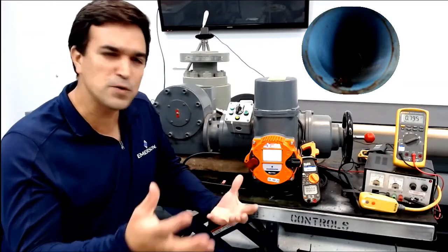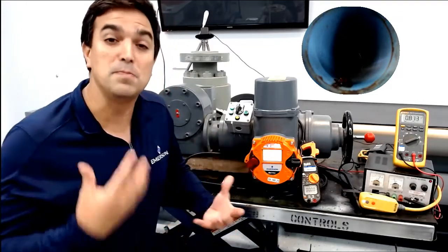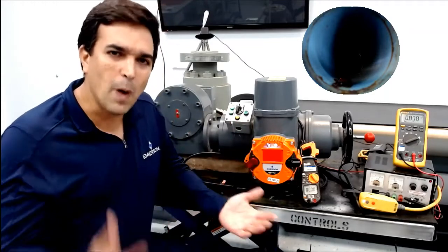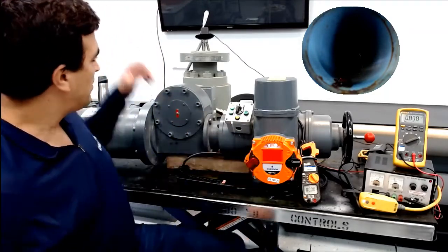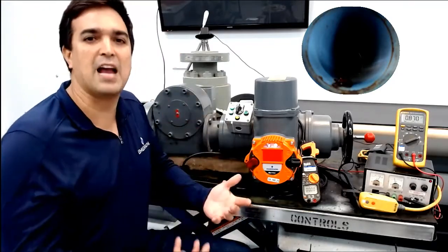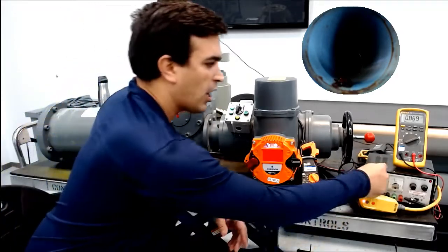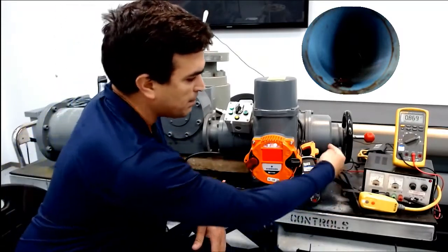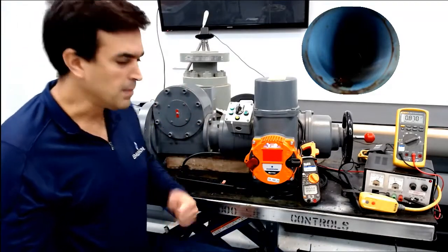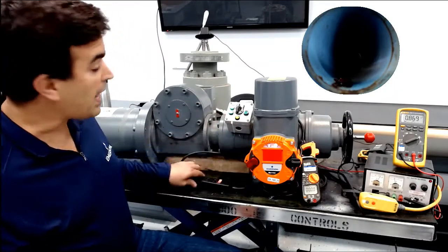So what is going to happen? In a few seconds, as soon as the capacitor loses power, you are going to see this screen red, which means, hey guys, we have a problem. We lost main power. So what is going to happen here? You lost main power, but the valve remains open, which is the main use of this kind of actuator. Now, if you want to trigger it, you can trigger in two ways. You can cut the 24 volt DC and remove power from the active brake, or you can trigger an ESD signal.